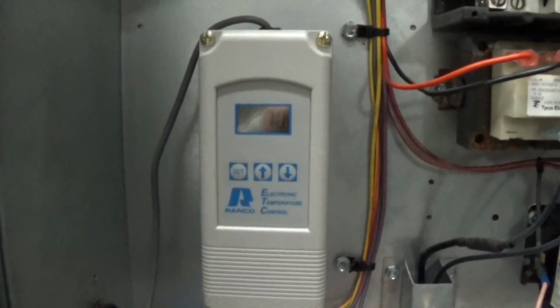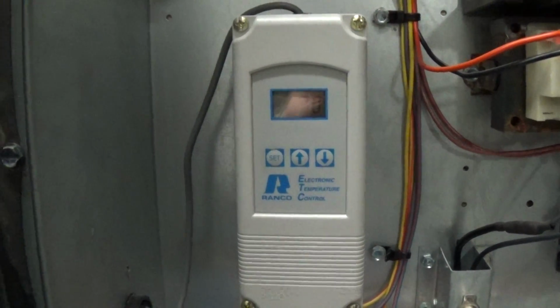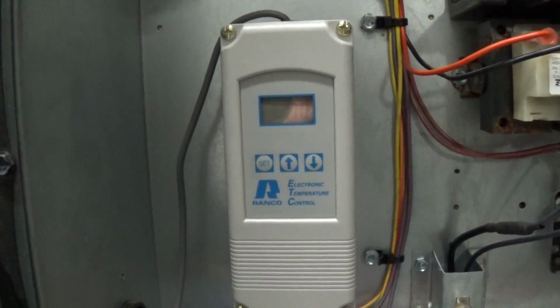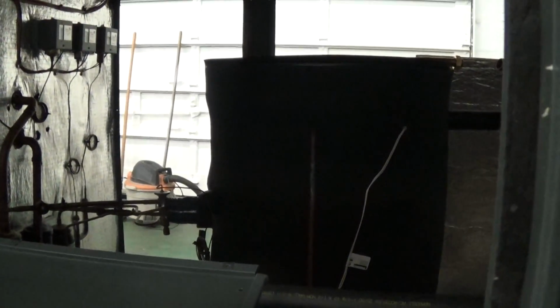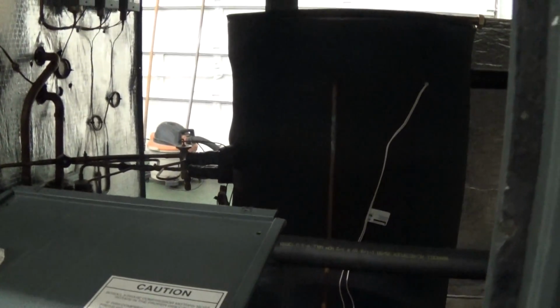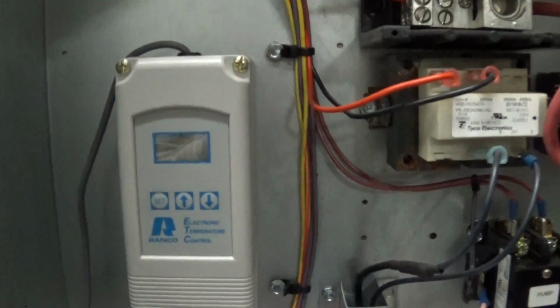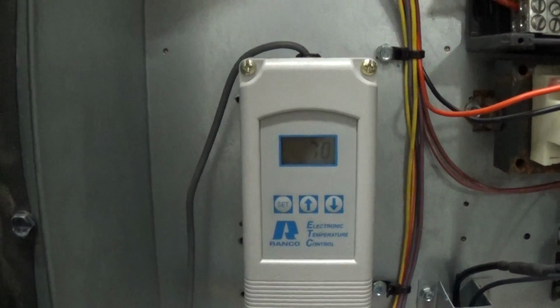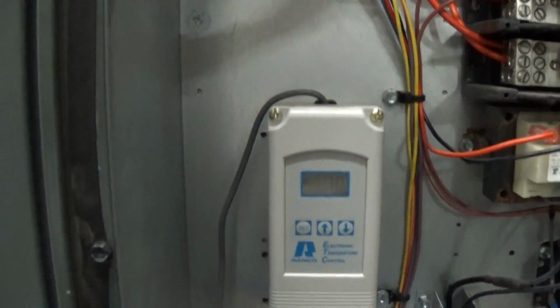In this case here, we just have a single pump drawing off the tank, and that's a 1 horsepower pump on this particular unit. We're going to talk about the Ranco controller a little bit. On this dual circuit, dual compressor chiller, what I'm going to do today is a couple different things, but first we're going to take this tank of glycol, which is about 30 or 40% glycol, about 55 gallons, and we're going to chill it down to about 28 or 30 F with both compressors on.